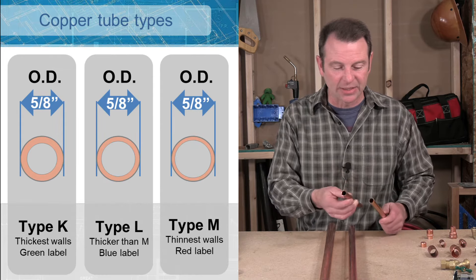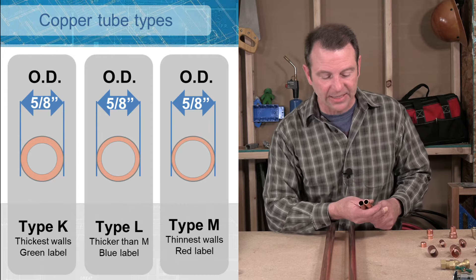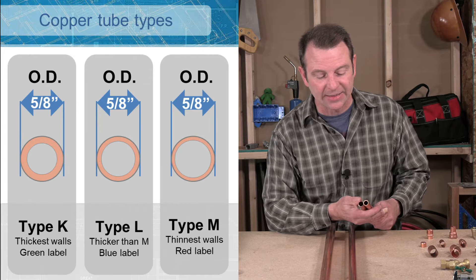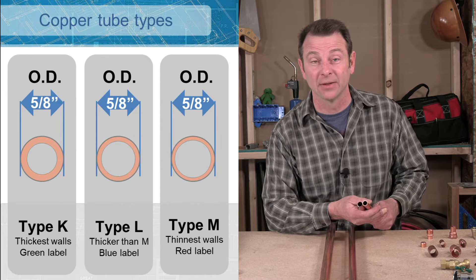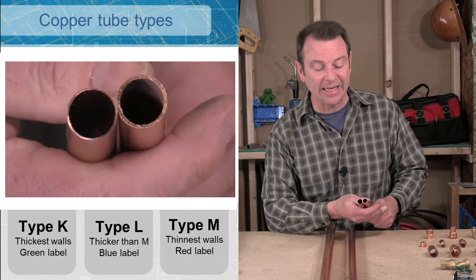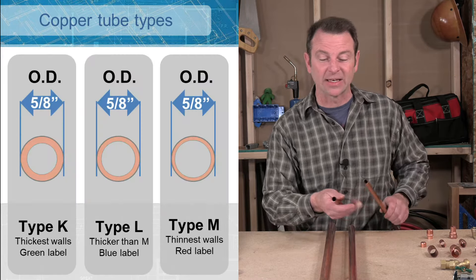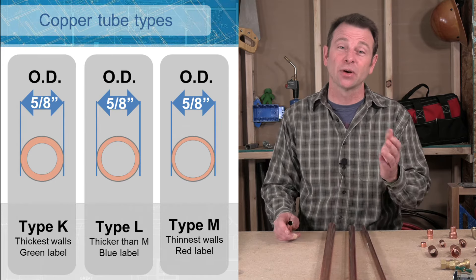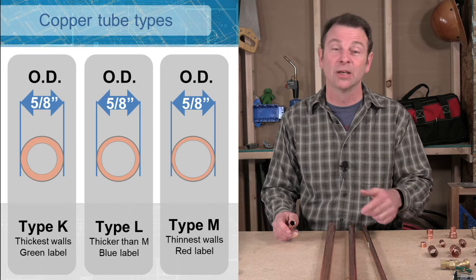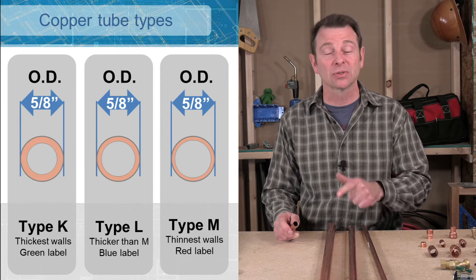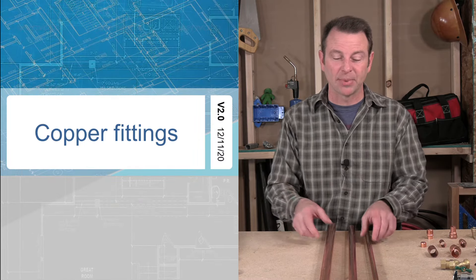I have here a type M, which is the thinnest, and I have a type L here. If I put them next to each other, you might be able to see that this type M is just a little thinner than my type L. If you go to a type K, it's even thicker than my L. I don't have a sample of that here today. Most of your type K is found in commercial installations. You'll see a lot of L and mostly M in residential building. So there's the basic on our copper pipe.